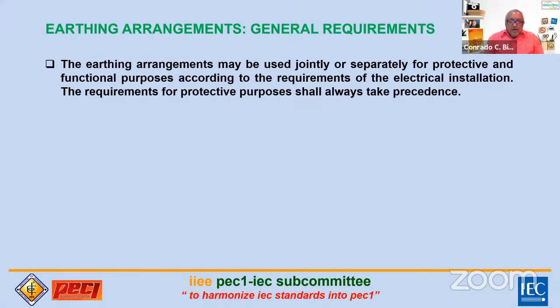But anyway, we won't leave the equipment with problems either. Of course there are criteria and rules on how to do earthing for data centers and our electronic equipment. That's already established. But other electrical practitioners shouldn't say it's not allowed to separate them, because that's not permitted. You'd be violating the requirements of the code and the earthing requirements of IEC. That's a violation. It states that protective measure takes precedence, it's most important.